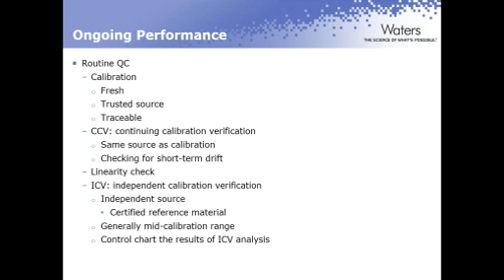You'll want to control chart the results of that ICV, most importantly, because that will help you to determine any kind of trends. Am I trending upward? Am I trending downward? Are all my results below the certified value or the mean? Are all my results above? It will help you to see and head off problems coming before that problem gets to a point where corrective action is necessary.